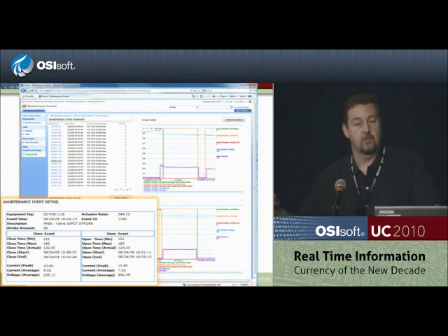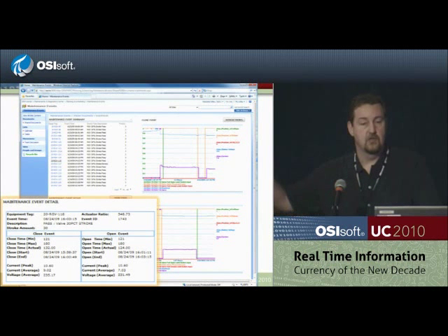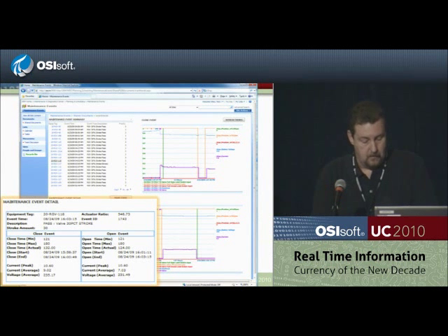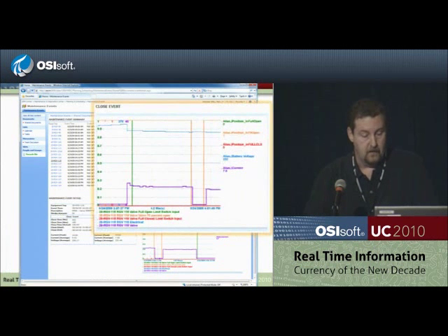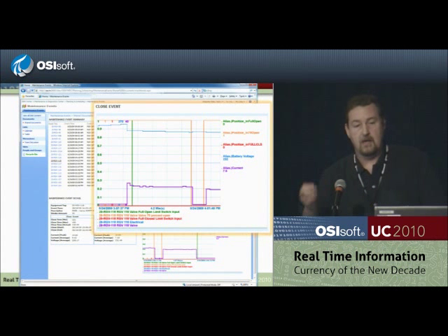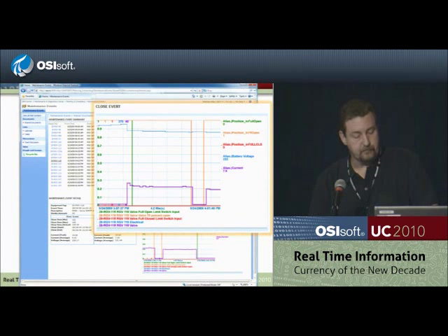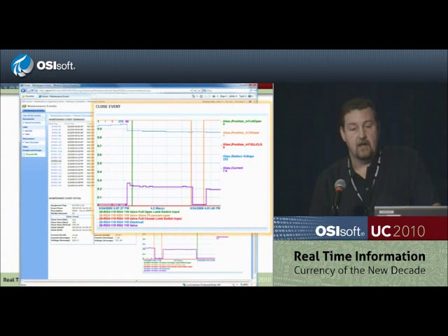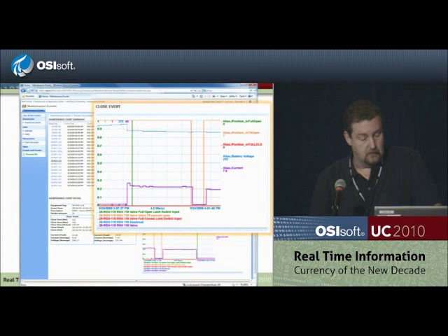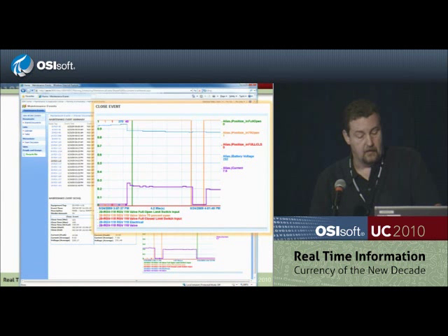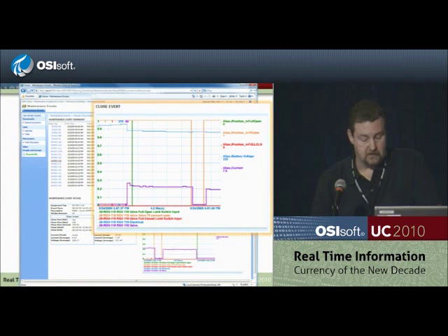We've moved all of these variables into Asset Framework. We run the ACE calculation and it draws the information out of Asset Framework — this satisfies all our maintenance and engineering requirements. The piece that goes to the DOT is the actual capture of the event. The vertical lines represent the limit switches on the valves, the blue line on top represents the voltage for that stroke, and the purple line is the current that the DC compound motor drew.